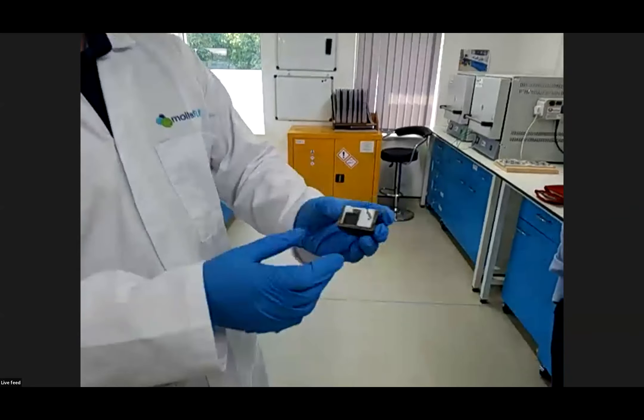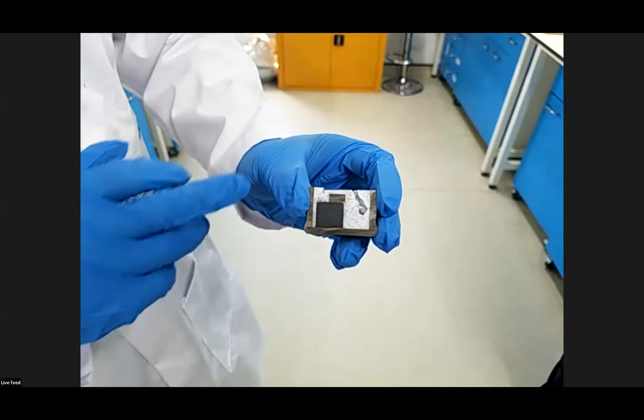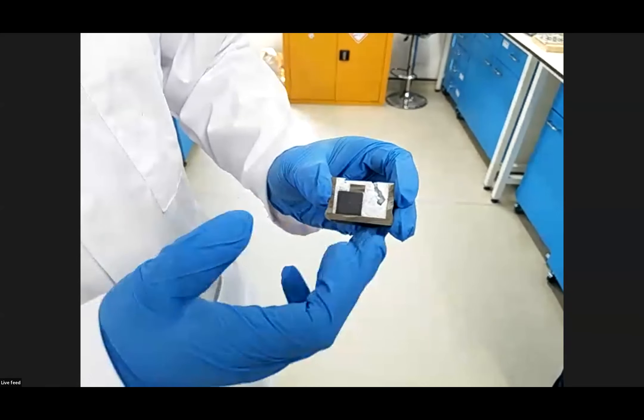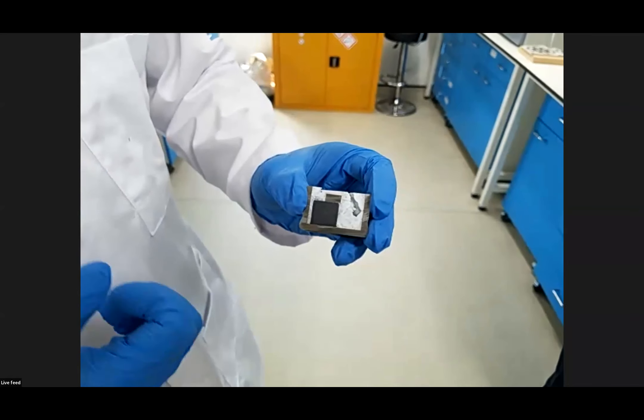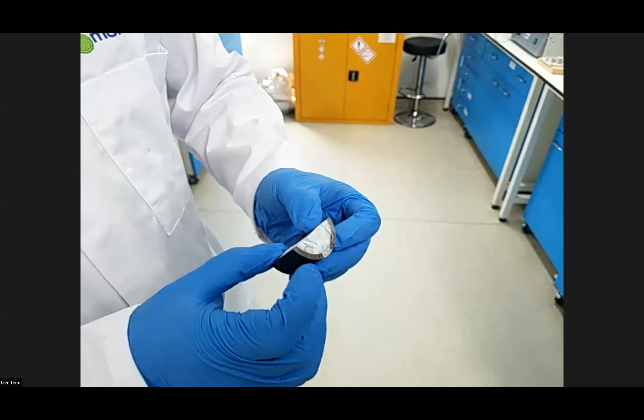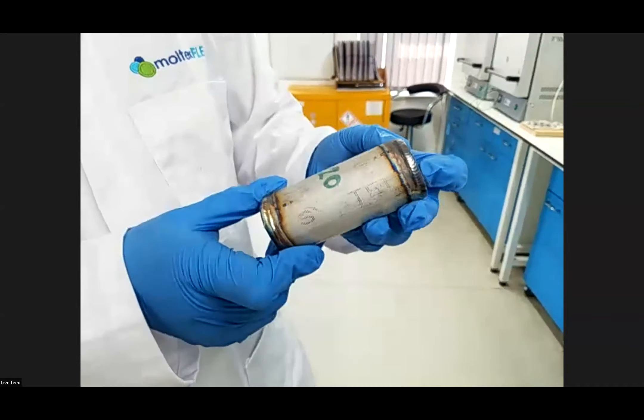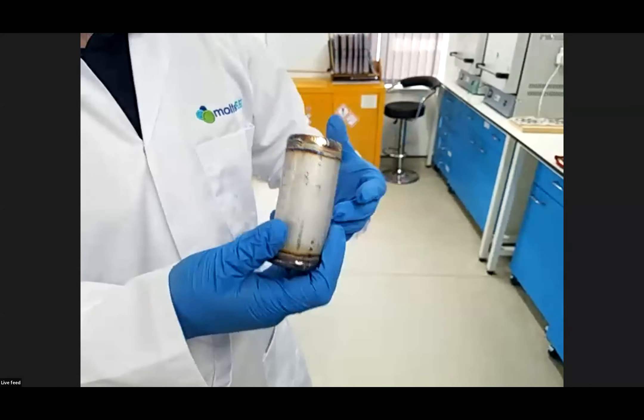In the past two years we've managed to get samples running continuously for the whole period for our coolant salt chemistry, and we have quite a lot of fuel salt chemistry on as well. We take small cylinders made from the materials you'd use for the reactor tank — we've got graphite as moderator, various steels for fuel cladding, and our salt: a simple fluoride chemistry salt with what I'll call our 'secret sauce' of base metal additives, which enable you to control corrosion without needing to go to hyper-purity. This is the inside section of a pin that's seen three months of service in the oven. We've made hundreds of these and inspected many of them.